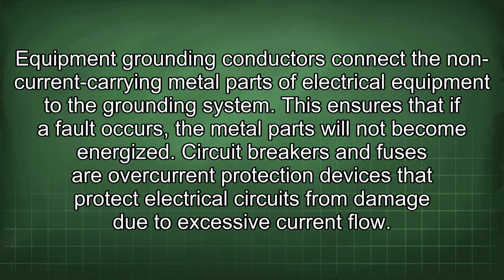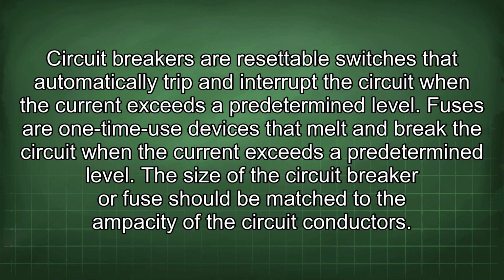Circuit breakers and fuses are overcurrent protection devices that protect electrical circuits from damage due to excessive current flow. Circuit breakers are resettable switches that automatically trip and interrupt the circuit when the current exceeds a predetermined level. Fuses are one-time use devices that melt and break the circuit when the current exceeds a predetermined level. The size of the circuit breaker or fuse should be matched to the ampacity of the circuit conductors.